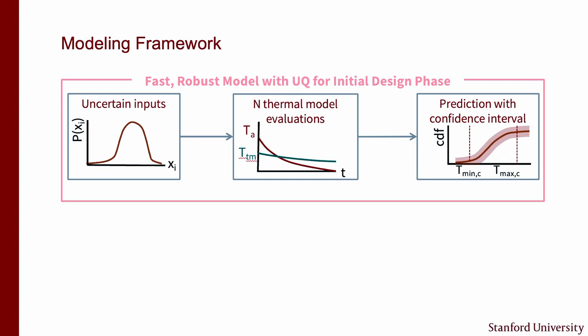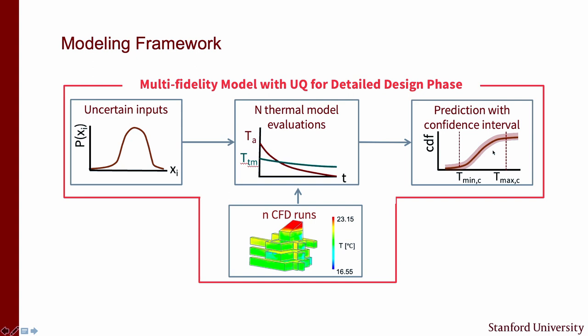When you move to the detailed design phase, all these uncertainties might result in quite wide confidence intervals that you want to reduce. That's where computational fluid dynamics comes in—giving a much more detailed solution for the flow field and temperature field, and letting you improve the correlations used in Energy Plus for heat transfer coefficients and natural flow rates.